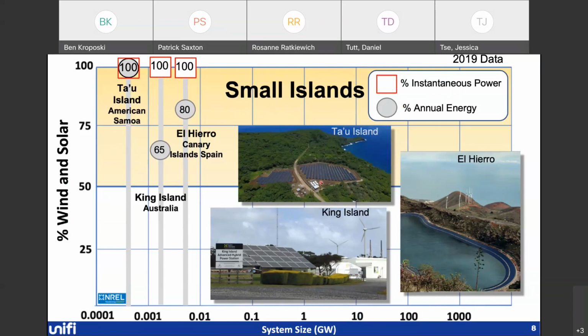Now, it has a very big battery, and it's got a very large solar system for the size load. This is a 150 kilowatt nominal load, and it has over a megawatt of PV, so about 10 times the load size in deployed solar, and then it also has a large battery on it. The other thing with these other island systems like King Island in Australia, El Hierro in the Canary Islands, they also have large amounts of energy storage. So you can see here this wind-focused system has got a pumped hydro plant associated with it. But in general, we can run these systems at 100% inverter-based grids.